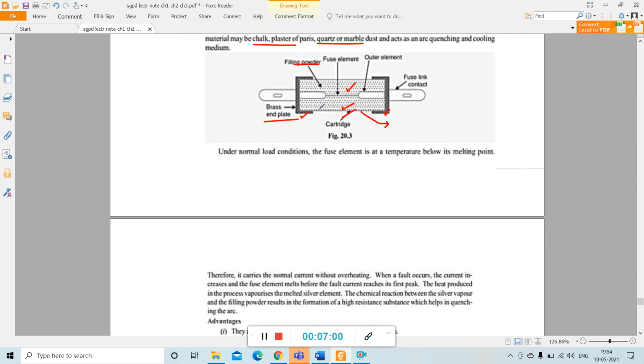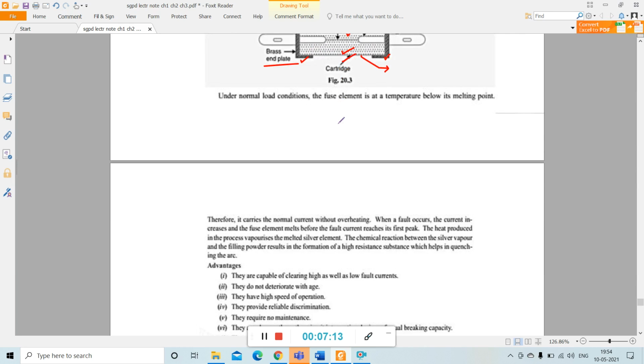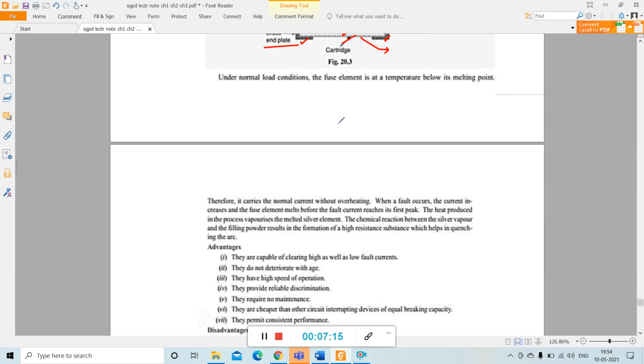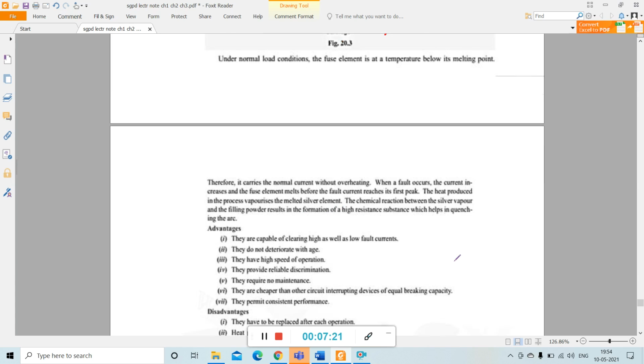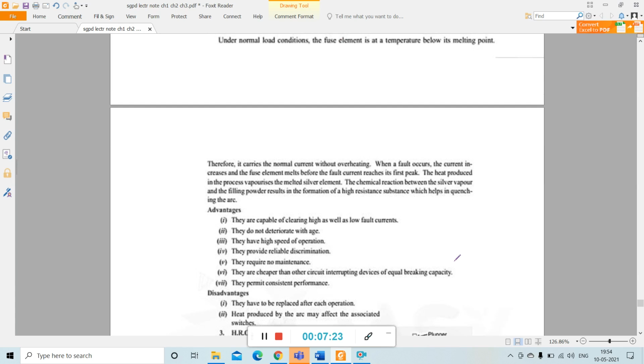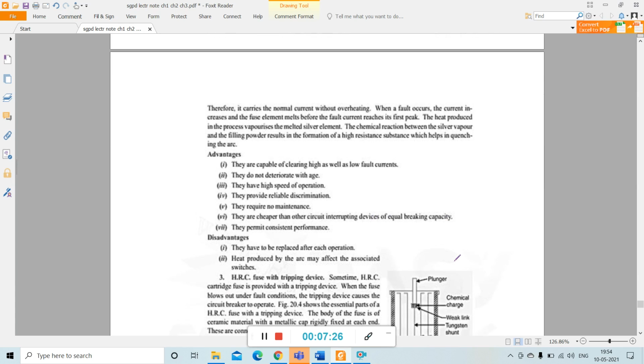See, this is a cartridge body, this is a brass end cap, and there is a fuse element surrounded by filling powder. Under normal conditions the fuse element is at a temperature below its melting point, so it carries the normal current without overheating. But when a fault occurs, the current increases and the fuse element melts before the fault current reaches its first peak.